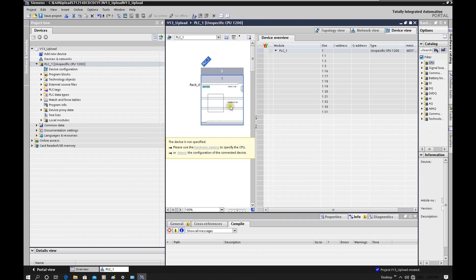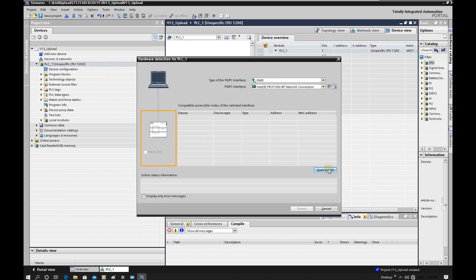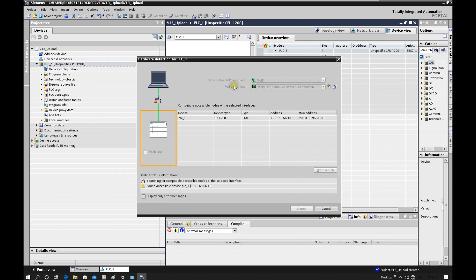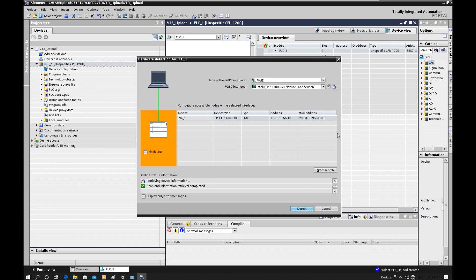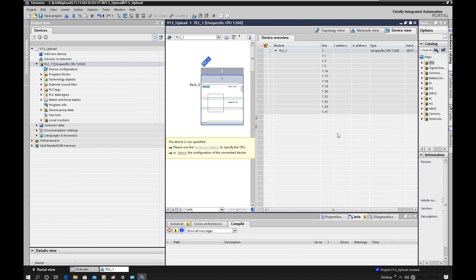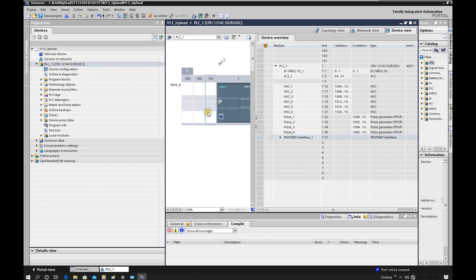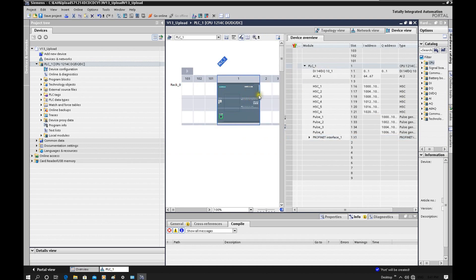After we select version 4.1 and create the specified CPU, let's click detect. Click start search — and keep in mind, select the correct PC/PG interface. The CPU is found. Let's do detect. Basically the idea is we will upload the CPU hardware configuration. Keep in mind this hardware configuration is only available for the main rack. Now this is the CPU hardware. Let's click go online.